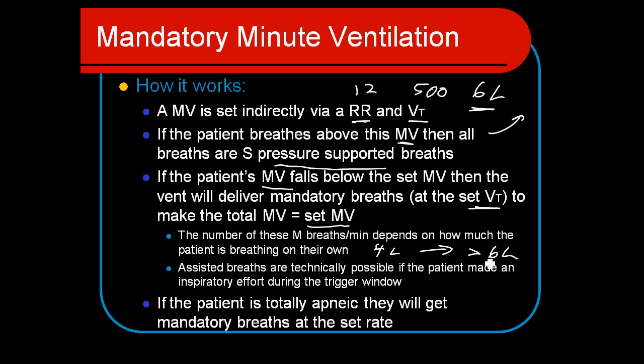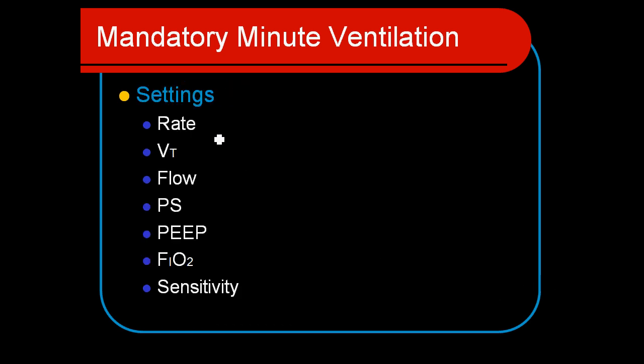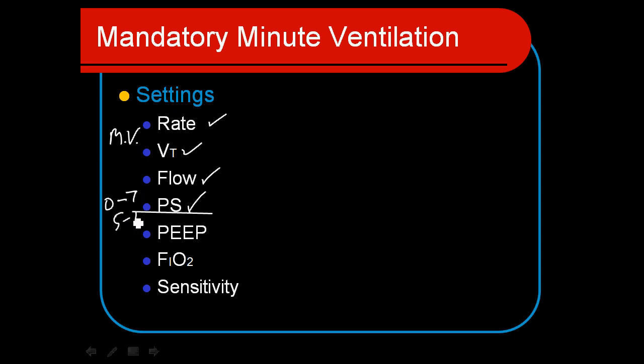Generally speaking, we establish this mode for patients who don't really require IMV or ventilatory assistance — they are fine on pressure support. We establish the minimum minute ventilation goal just as a safety net. Like many modes, we set the rate and tidal volume to establish the required minute ventilation. We may or may not set the flow depending on the manufacturer. We set up a pressure support level, which could theoretically be zero but is generally set at five to seven centimeters to overcome the work of breathing through the endotracheal tube, or as high as 12 cmH₂O to augment inspiratory efforts.